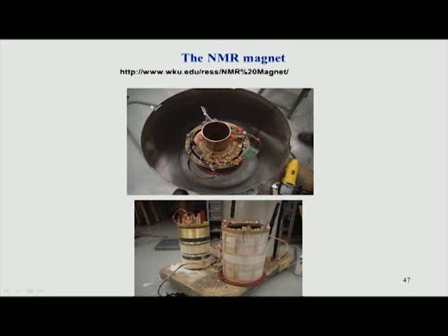So, you see this container here which is surrounding this coil is the innermost, and you fill liquid helium around this, and liquid helium basically keeps this whole current and the coil in the superconducting state. And then around this particular container you fill one more container which has a vacuum, so that this liquid helium inside does not evaporate, because we want the liquid helium to stay there and not evaporate very rapidly. Therefore, we surround it by a vacuum, and then also we surround it by liquid nitrogen, which is another layer of Dewar around this.